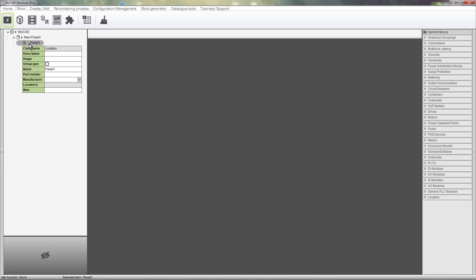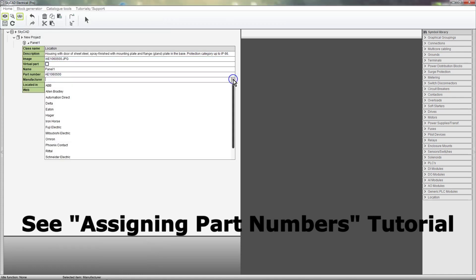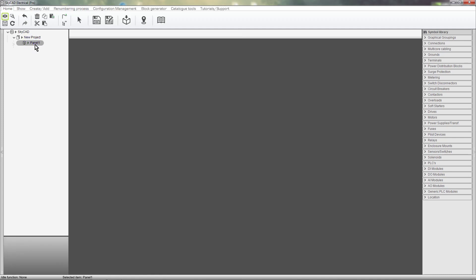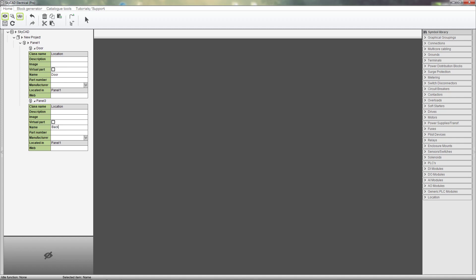So let's enter the details of the new enclosure we want to use. To add sub-locations, such as a door and a backplate, select the enclosure, click on the Create Add tab and select New Location. Let's add two of them — one for the door and one for the backplate — then rename them accordingly. You can define part numbers for these sub-locations too, or assign part numbers from the catalogue. In this case, I won't do that because I know this enclosure part number includes the door and the backplate. So I'll be sure to check the virtual part properties so that these parts do not show in the parts list and bill of material — they will be considered part of the enclosure part number.